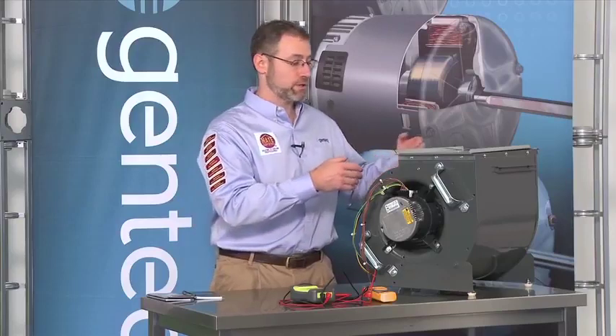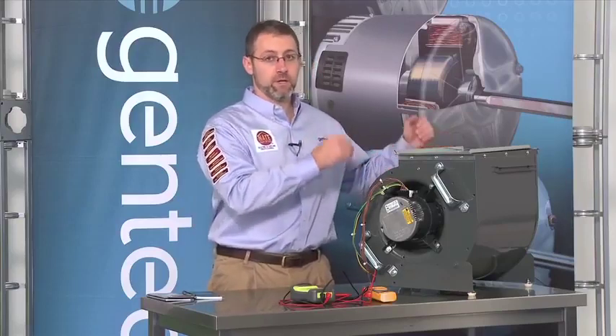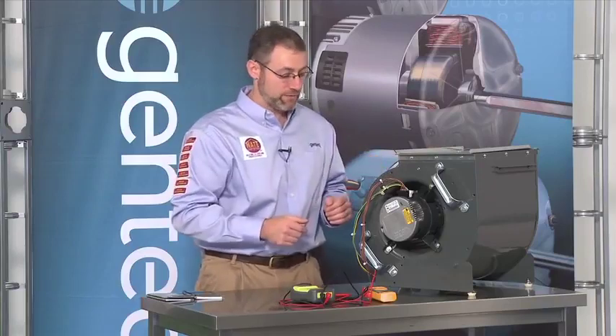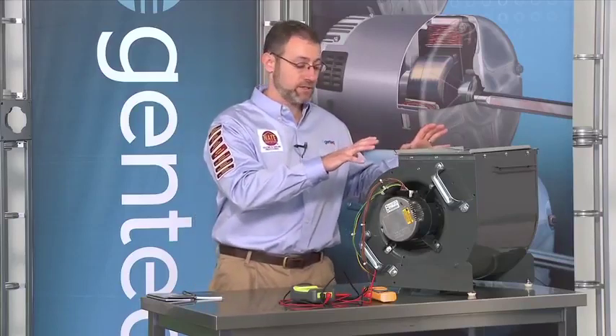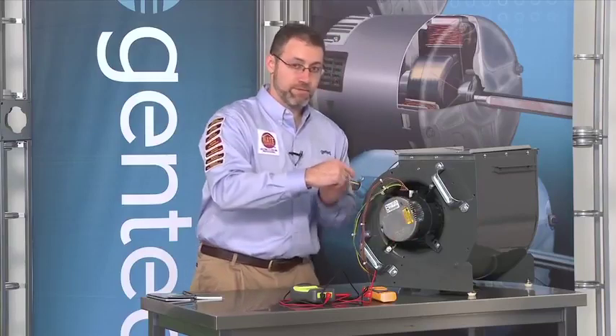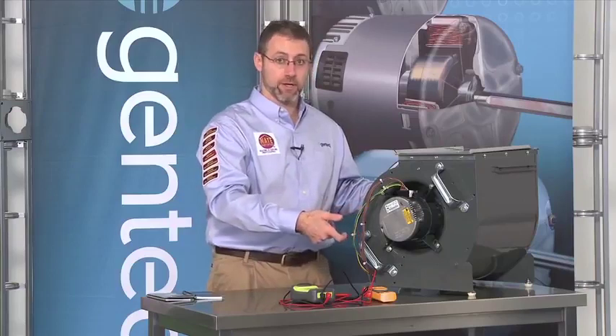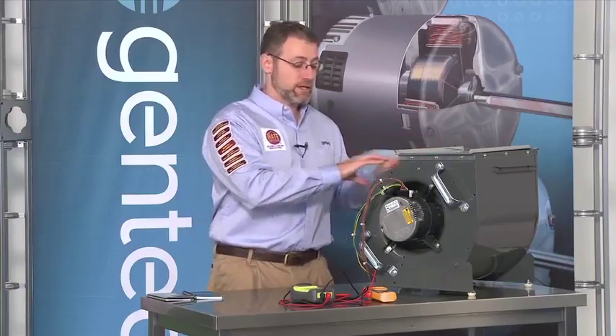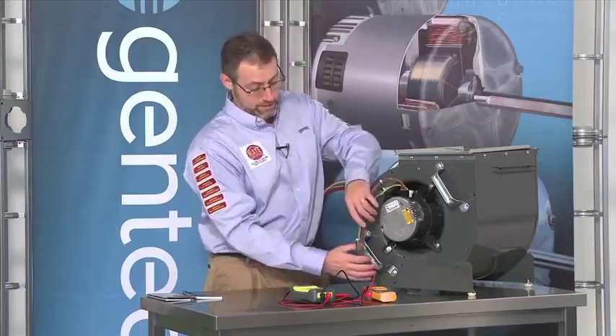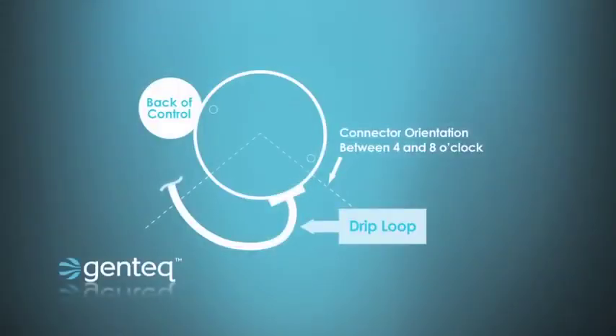Just like any motors, we want to make sure that when we replace a motor that we center the blower wheel, we tighten the hub nut on the wheel on the flat part of the shaft, and like all of our ECM motors, we want to make sure that when this blower section is going to go back into the HVAC system, that this motor and these connectors be facing in the down position, or at least between the 4 and 8 o'clock position. So if this was the way this blower section was going back in, it would be incorrect. We'd need to turn the motor 180 degrees. If this were going into a downflow furnace, then it would be perfect, because this blower section would be turned completely upside down and the connectors would be facing down. And then of course we also want to make a drip loop out of our motor harness so that no water can drain off of the wires and run right down into the connections themselves.